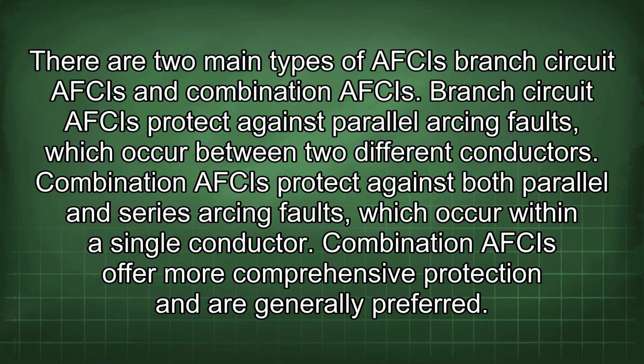There are two main types of AFCIs: branch circuit AFCIs and combination AFCIs. Branch circuit AFCIs protect against parallel arcing faults, which occur between two different conductors. Combination AFCIs protect against both parallel and series arcing faults, which occur within a single conductor. Combination AFCIs offer more comprehensive protection and are generally preferred.